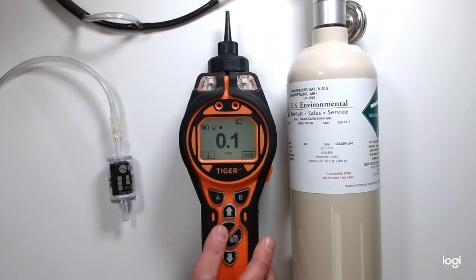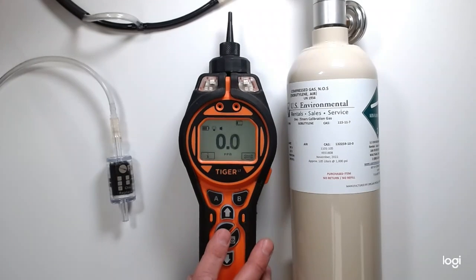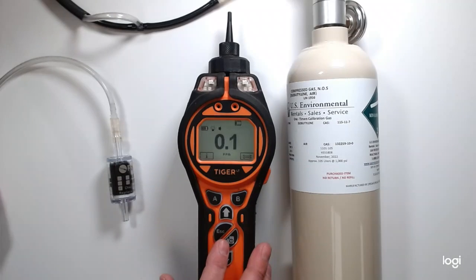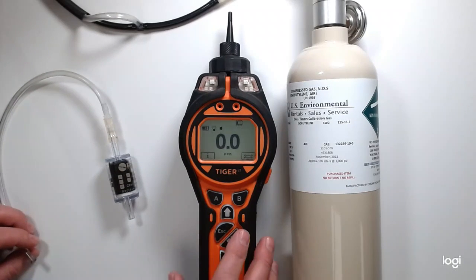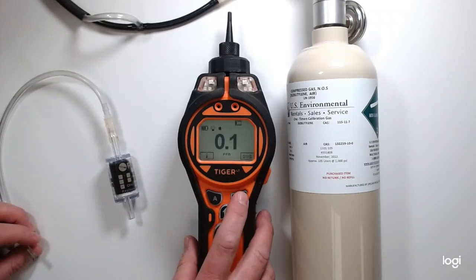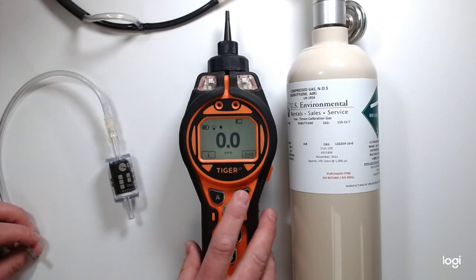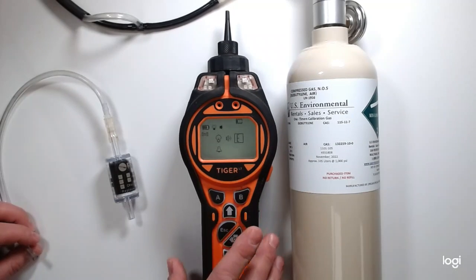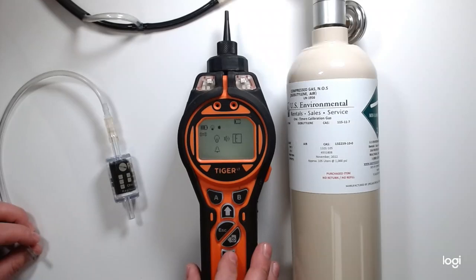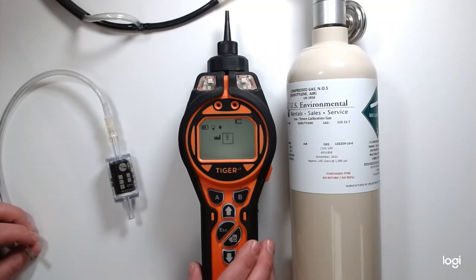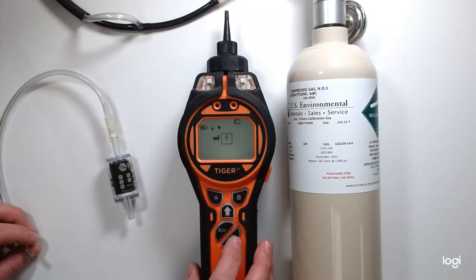Hit escape to cancel the alarm. Once you know that you have good suction and a tight seal, you can then proceed to the calibration. We start by hitting the monkey wrench, which would be the letter B, and we move our cursor over to the ruler and hit the enter. We're doing a manual calibration, so we will click on the little stick figure and hit the enter button.